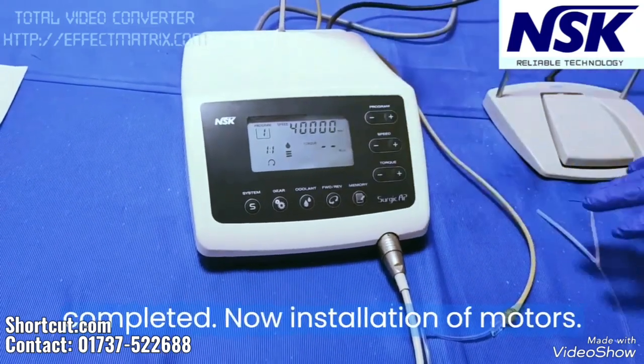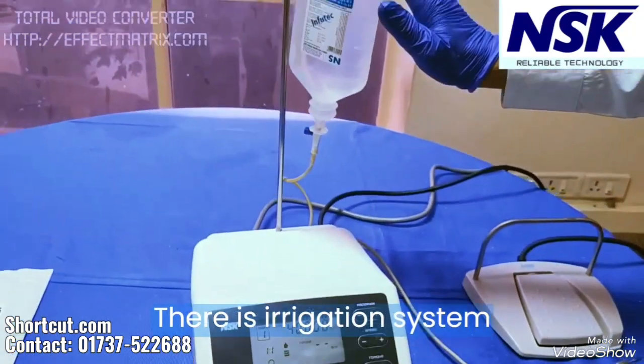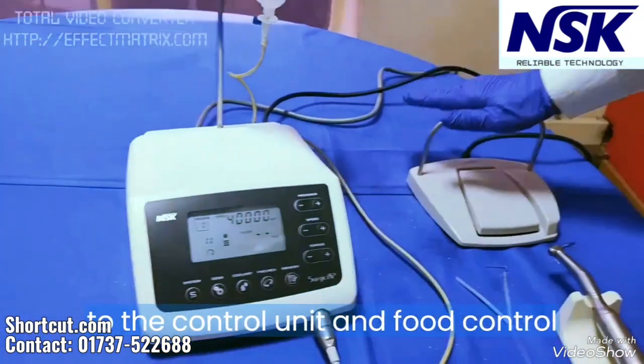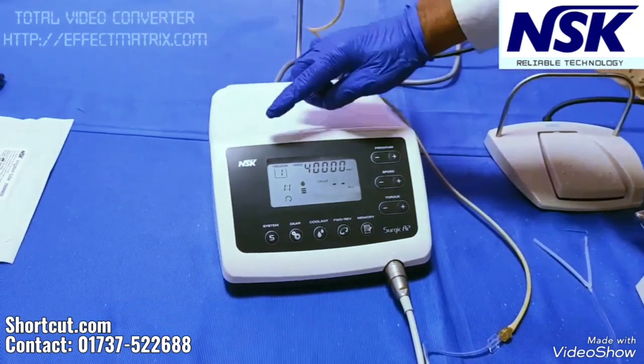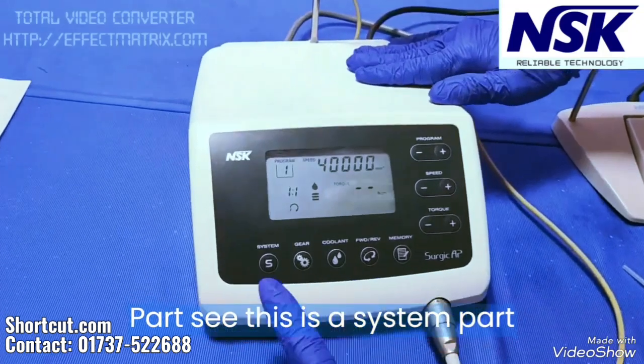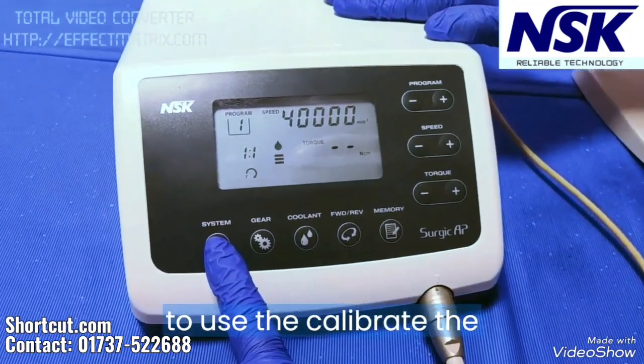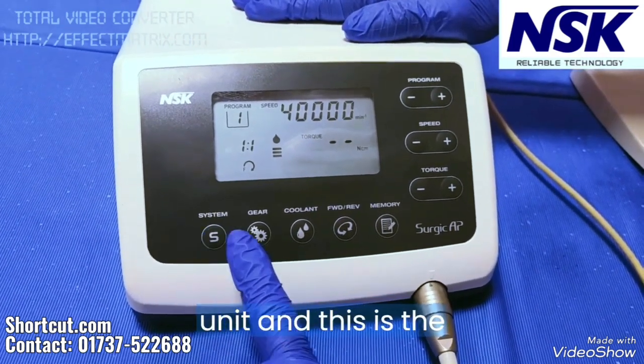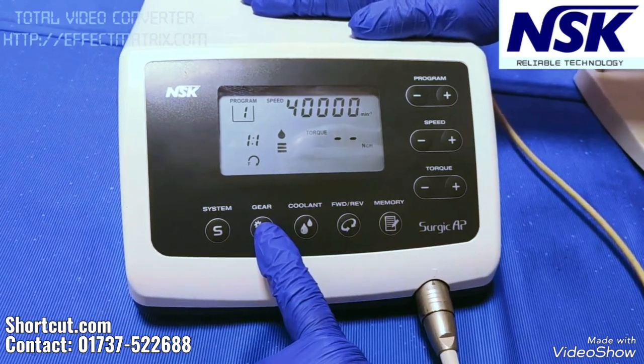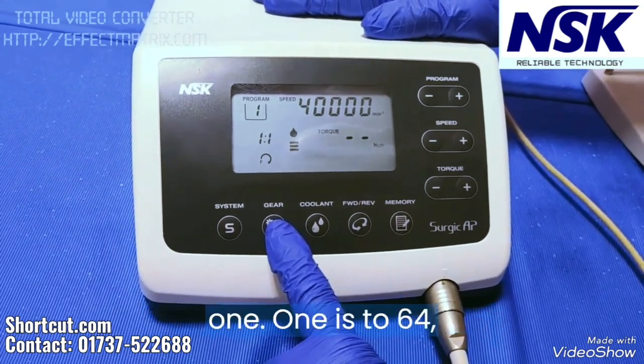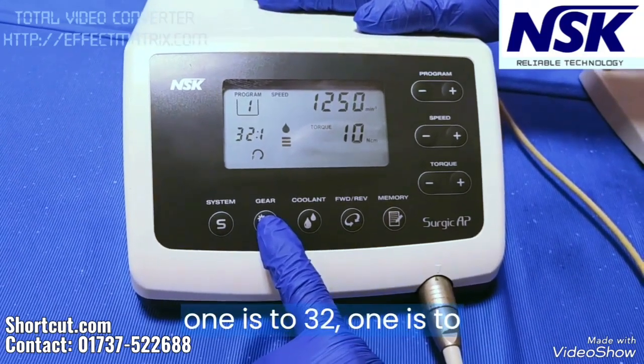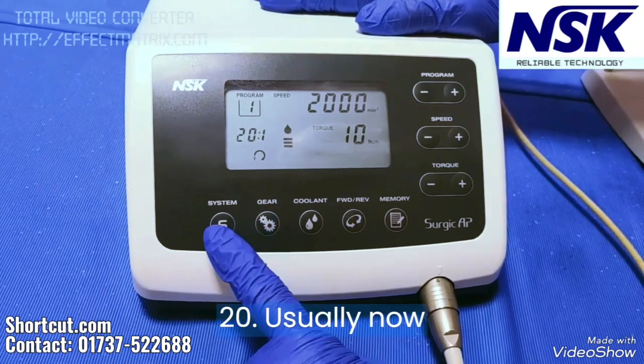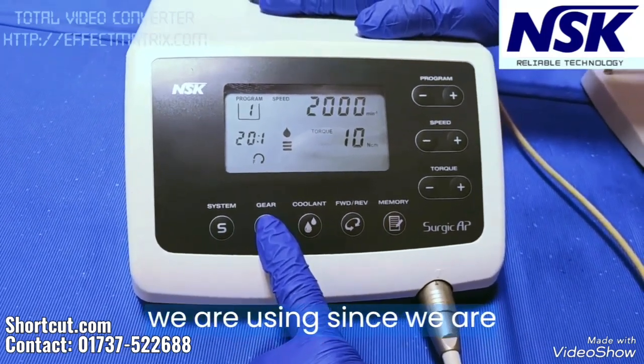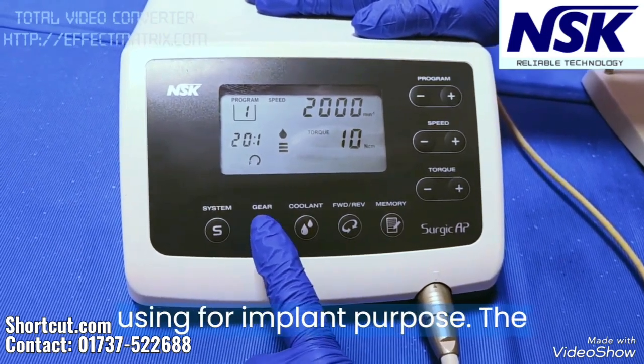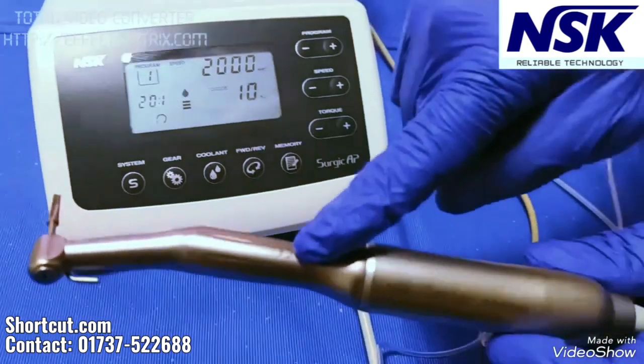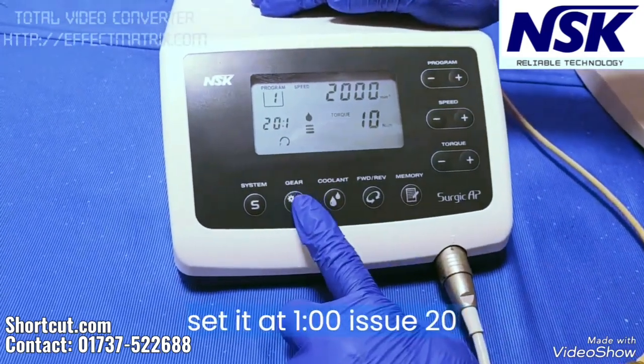Our installation has been completed now: installation of motors, irrigation system to the control unit, and foot control connected. Now I am explaining the display part. This is the system part to calibrate the unit. And this is the gear system to change the handpiece gear: 1:1, 1:64, 1:32, 1:20. Since we are using it for implant purposes, the handpiece is 1:20, SMAX ST20. We have to set it at 1:20.